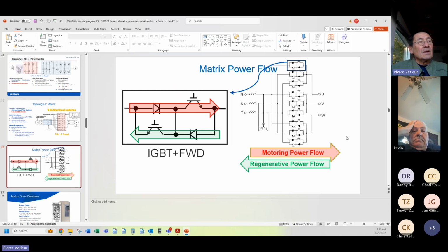And if you turn on, let's say we turn on from R, we just turn on this transistor right up here and connect it to U. From S, we turn on this transistor and we connect it to V. And T, we turn on this transistor and we connect it to W. We have basically a 3-pole contactor. This transistor gates on and stays on. It doesn't pulse. The matrix drive can be made into a contactor, directly connecting the motor to the line.